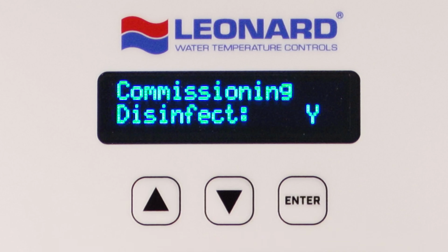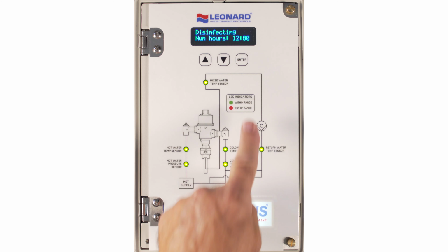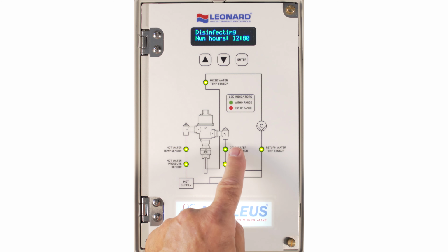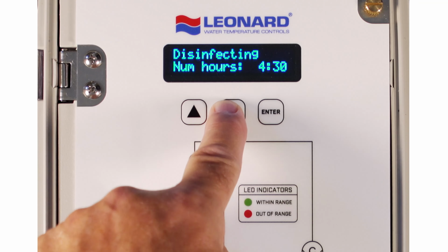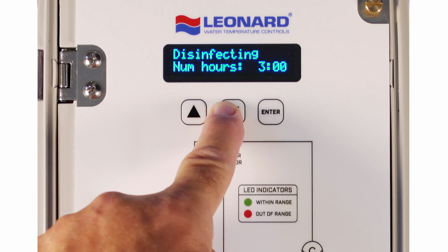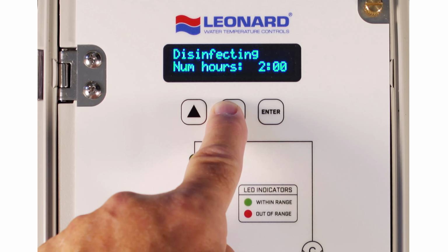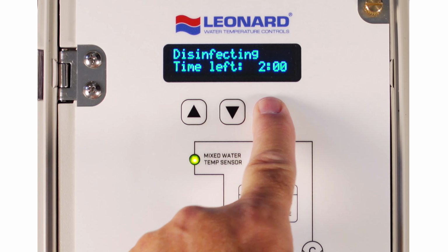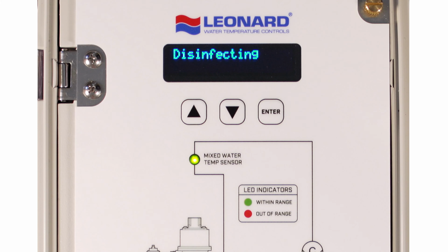Once Y is chosen, the authorized user will then be prompted to enter the desired disinfection time. Adjustable in 15-minute increments up to 12 hours. Choose the desired time and press Enter to start the timer. Extreme care must be taken during the disinfection process. Disinfection can be canceled at any time by pressing the Enter key.